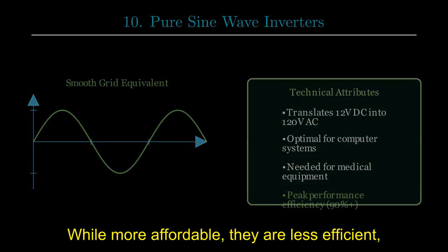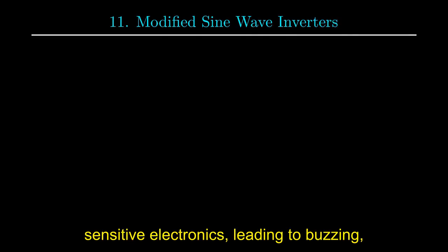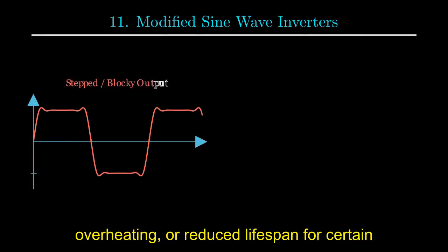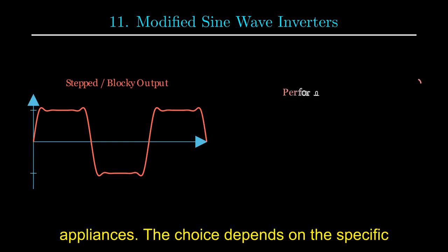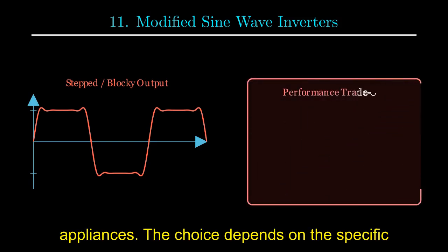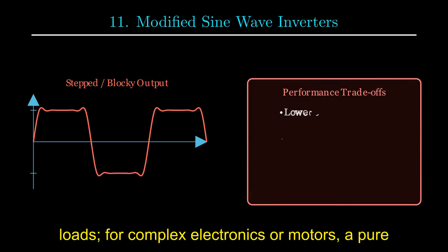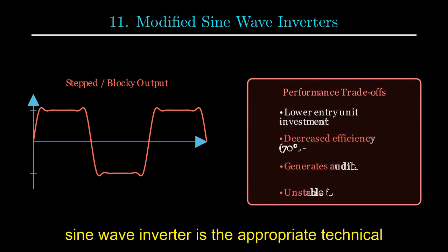While more affordable, they are less efficient, typically 70 to 80%, and can cause issues with sensitive electronics, leading to buzzing, overheating, or reduced lifespan for certain appliances. The choice depends on the specific loads. For complex electronics or motors, a pure sine wave inverter is the appropriate technical choice.